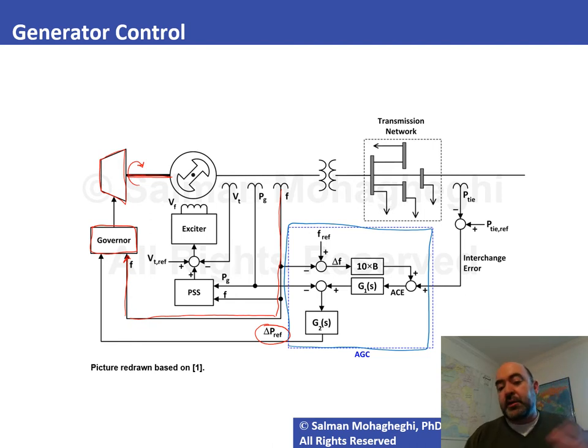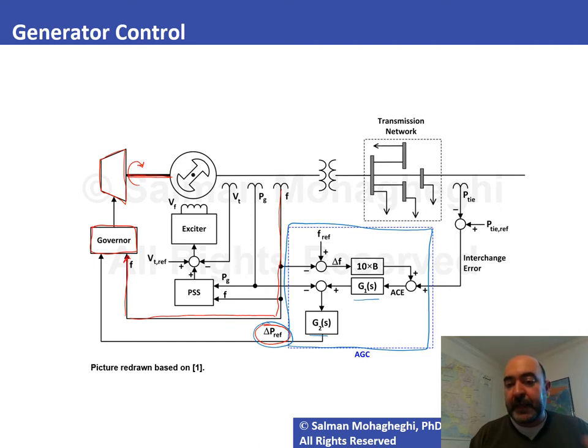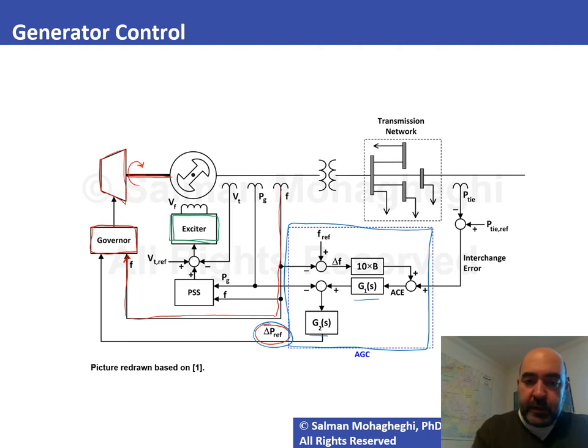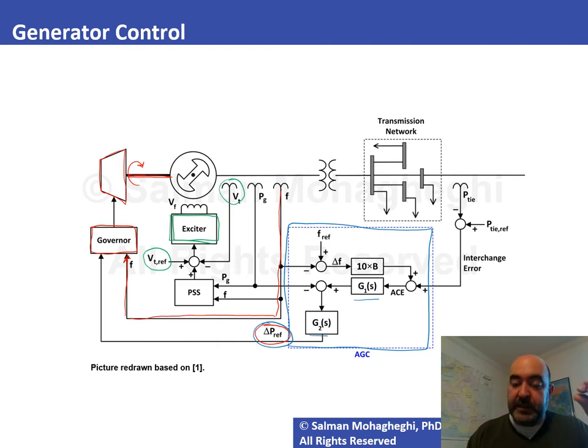AGC is a topic for future lectures. At a high level, the error in frequency and error in tie-line power collectively generate an error signal used through controllers to produce Δ P_ref. The excitation system monitors terminal voltage, compares it with the reference (typically 1 per unit), and feeds the difference as an error to the excitation system, forcing the field voltage up or down to keep V_T at one per unit.